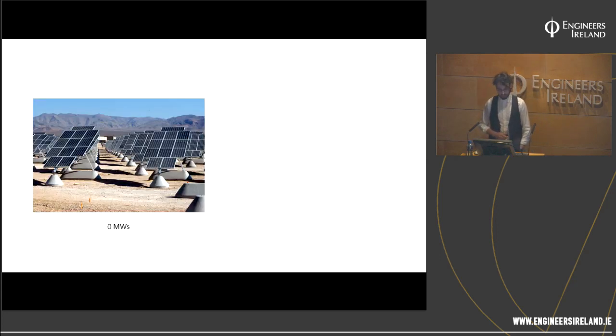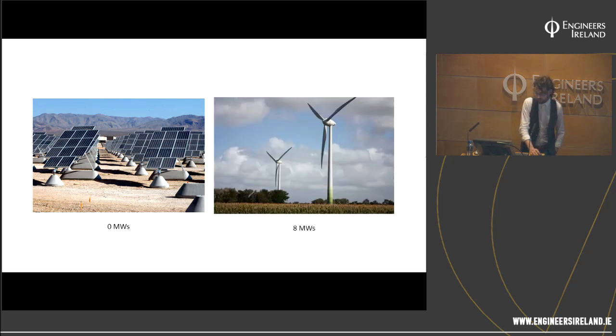So then we move on to our new technologies. PV has no rotating mass, hence it has no stored energy. Okay, simple as that. Now, wind turbines do have stored energy because they have a rotating mass. Those blades are turning. It's probably a bit of an unfair comparison, to be honest, because one wind turbine is a small MVA. You're going to have thousands of wind turbines on your system, so when you aggregate that stored energy it will be much higher. Except there's a caveat.